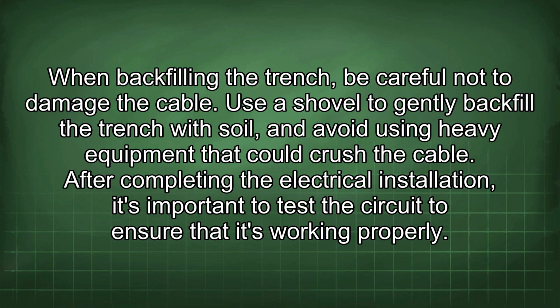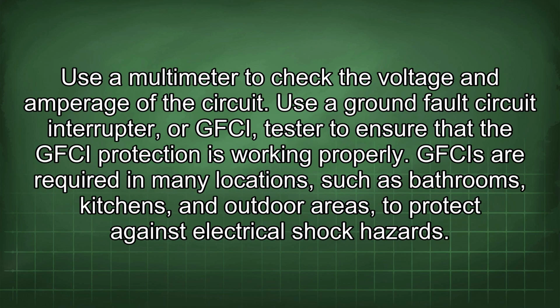After completing the electrical installation, it's important to test the circuit to ensure that it's working properly. Use a multimeter to check the voltage and amperage of the circuit. Use a ground fault circuit interrupter or GFCI tester to ensure that the GFCI protection is working properly. GFCIs are required in many locations, such as bathrooms, kitchens, and outdoor areas to protect against electrical shock hazards.